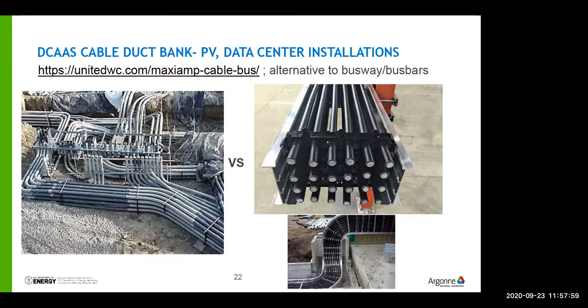But I don't see that on the overhead distribution lines. I see 4 lines, my 3 phases plus my neutral, go over, and then there are taps that come off to go to my low voltage transformer, and from there other taps in parallel feed 6 houses or whatever the breakdown is, tapped off of wires. So a wire with an insulation piercing tap feeds multiple circuits. It doesn't have a conduit and a disconnect. On the right are these bus ducts, and this is how the photovoltaic world works.